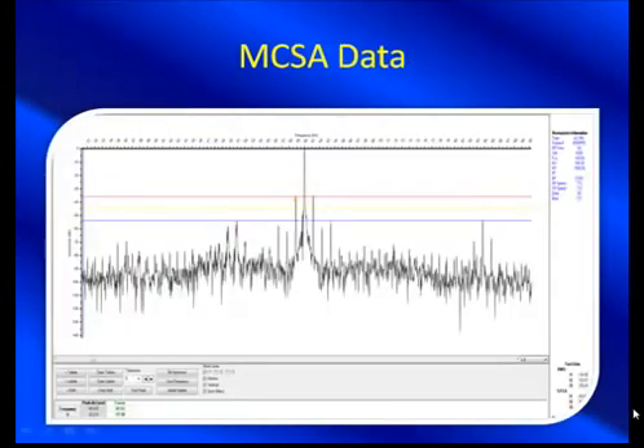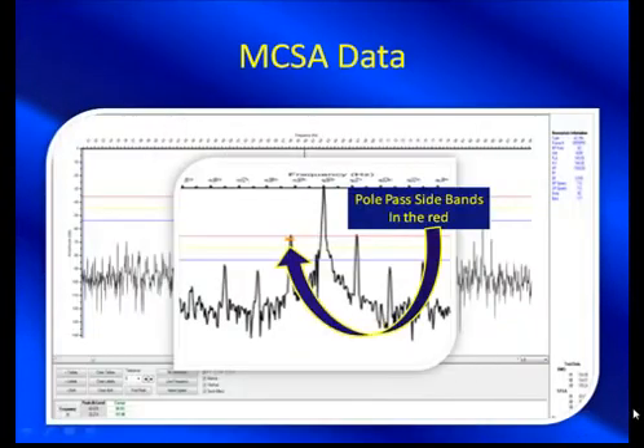Here's some data that they pulled. Right away, what jumps out? Look at that sideband — the pole pass sideband, which is a rotor bar defect indication. But one of the things we always tell people, if you've been following our tip of the week, there's more than one indication of rotor bar defects, and this is just one. It can be misleading if there are mechanical variations that are part of the design. But still, it's way up at the red line — approaching the alarming condition and certainly deserves a lot of attention.